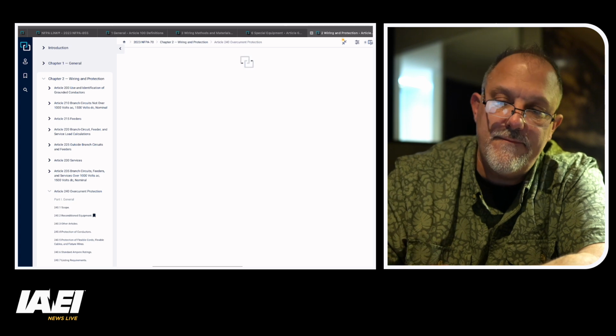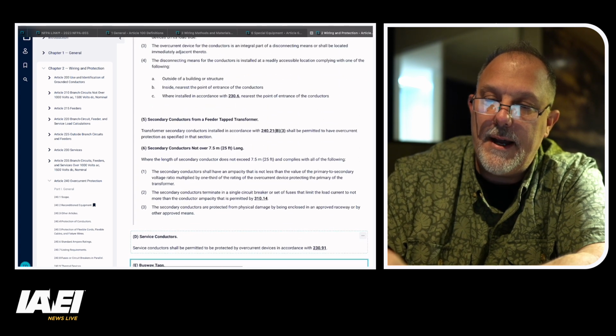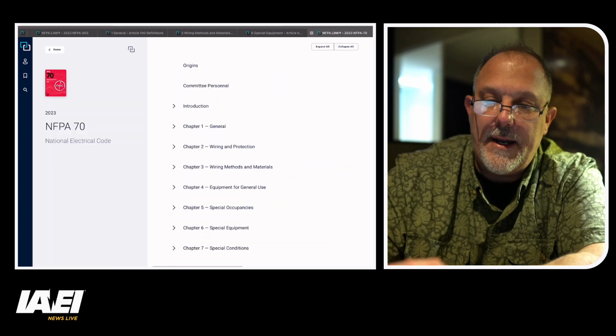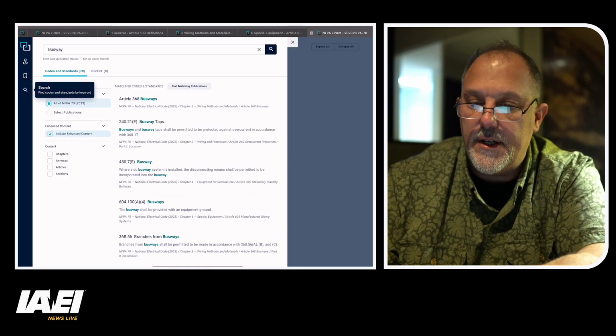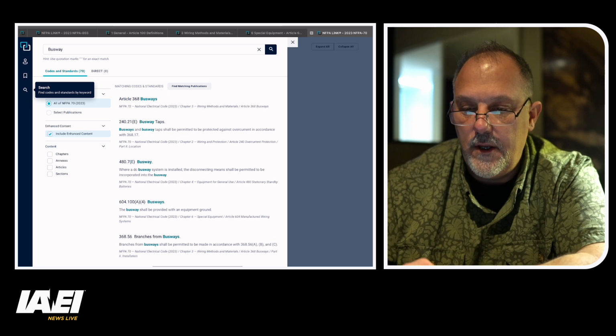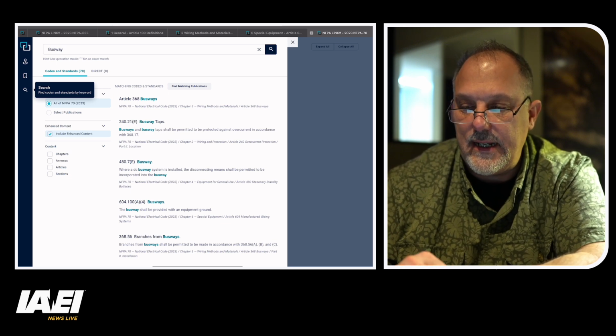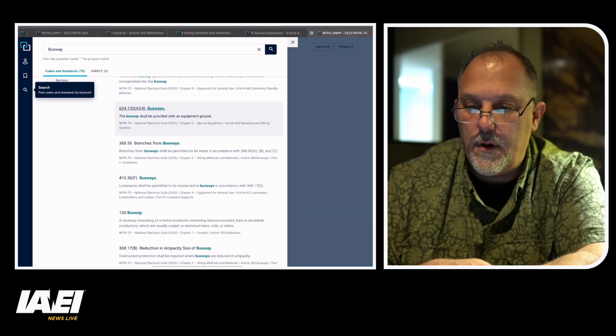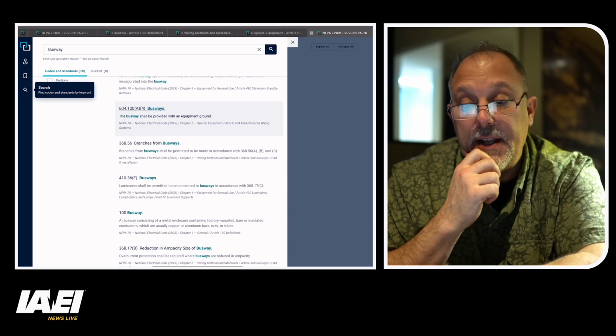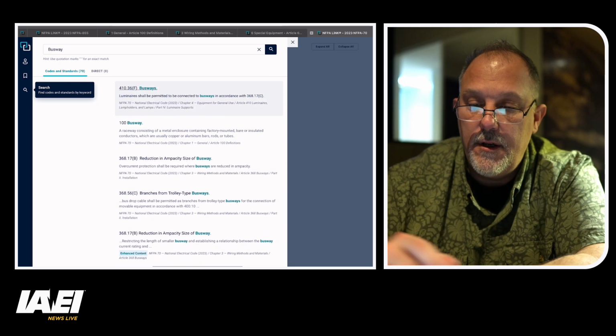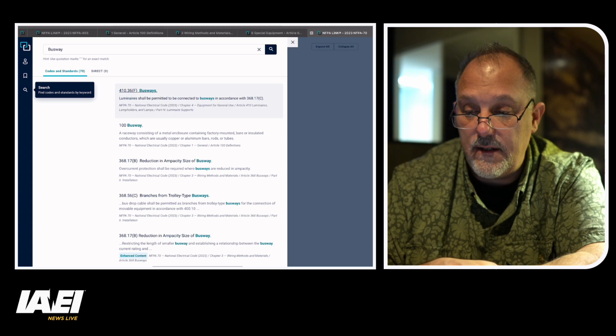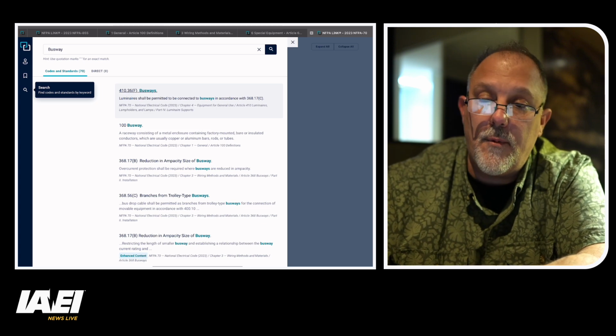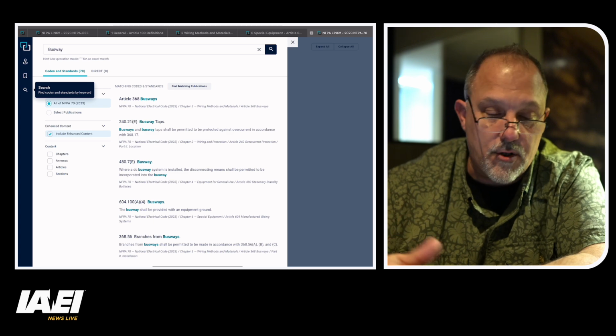Let's go back here, go back to search. Busway, you've got it in Article 240. You've got it in 480, that's for DC. 604, 368, 410 for luminaires. You have the definition of busway, 368. So what I'm looking for is other areas in the National Electrical Code where you might have busway be required to be listed, and I'm not seeing it.